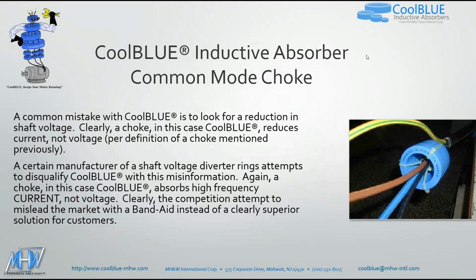A common mistake with CoolBLUE is to look for a reduction in shaft voltage. Clearly, a choke, in this case CoolBLUE, reduces current, not voltage. So it's a current device, not a voltage device. A certain manufacturer of shaft voltage diverter rings attempts to disqualify CoolBLUE with this misinformation. Again, a choke, in this case CoolBLUE, absorbs high-frequency current, not voltage. Clearly, the competition attempts to mislead the market with a Band-Aid instead of a clearly superior solution for their customers.